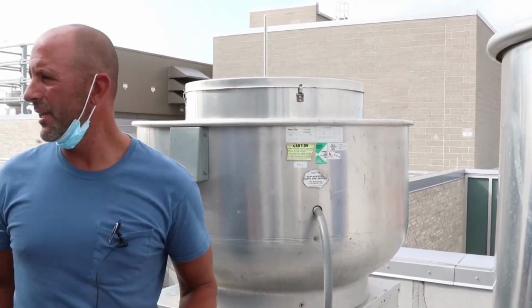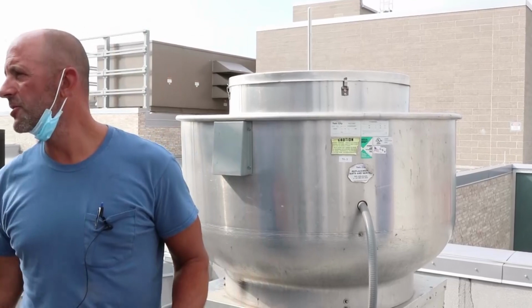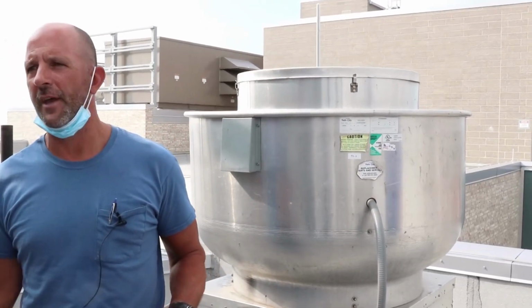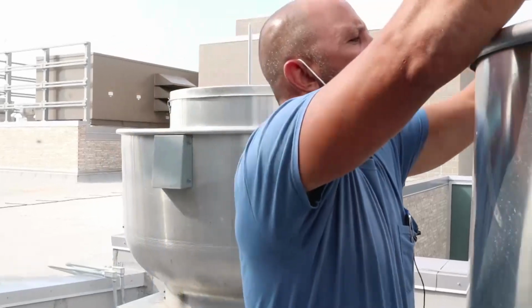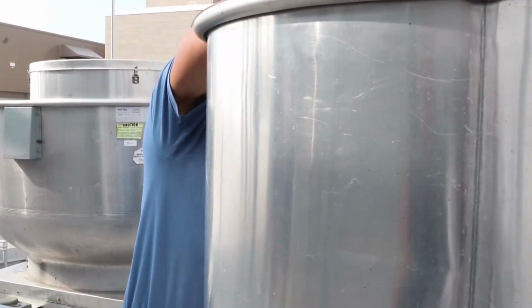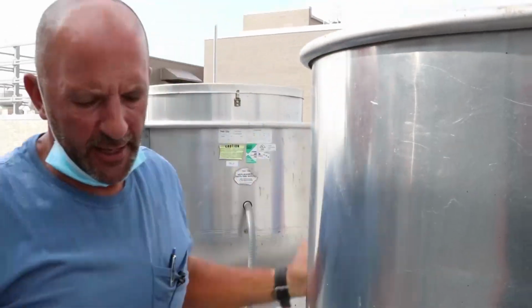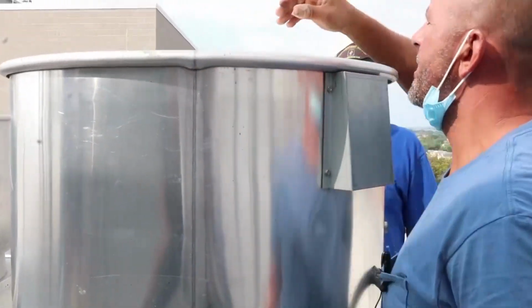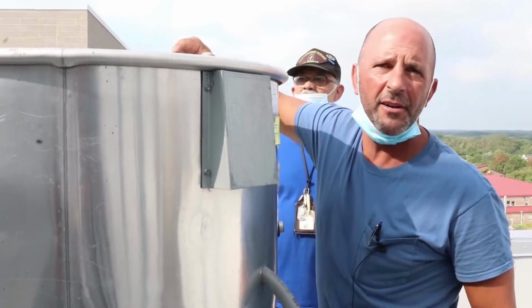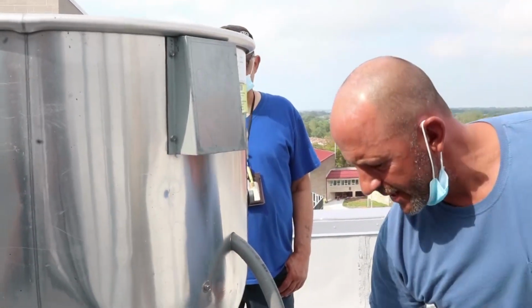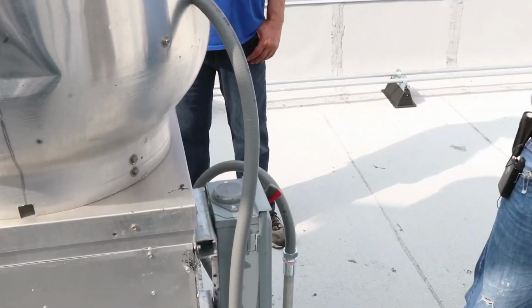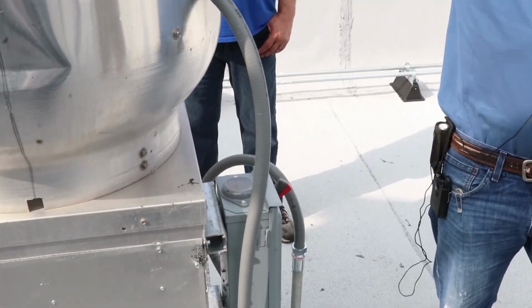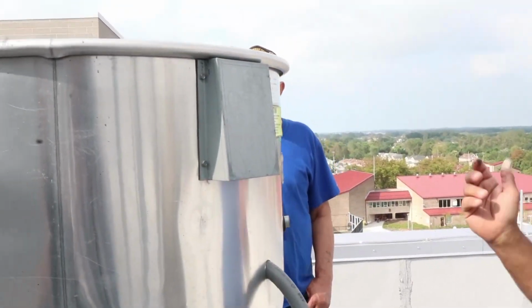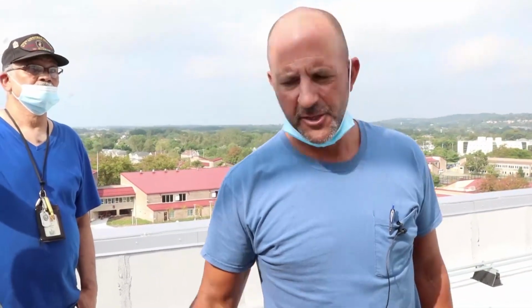So the only different fan you're going to see up here is a dryer exhaust, which we'll go look at. That will be the only direct drive fan, which is right around the corner. Once again, the cap goes on with spring-loaded clips. Just make sure you catch the ridge, because if you leave one or two of them off and the wind comes, it'll fling them right off. Disconnect. Make sure your fingers aren't in there. So this one did start. Like I said, sometimes when they're on a drive and you slow them down or stop them quickly, you'll get a fault at the drive just because it saw the loss of a load. You go downstairs, hit the reset, or just restart. It doesn't happen all the time.